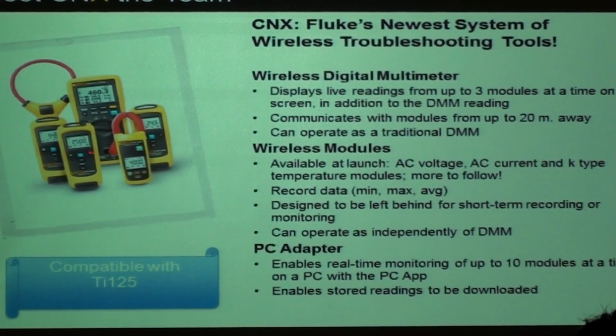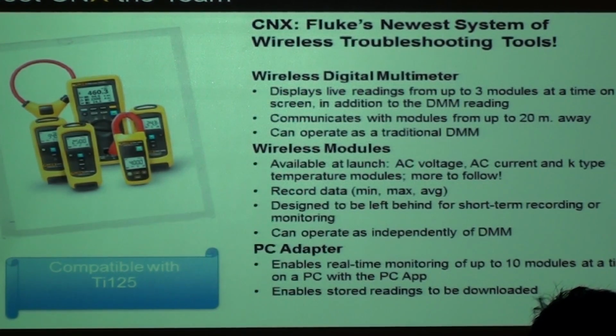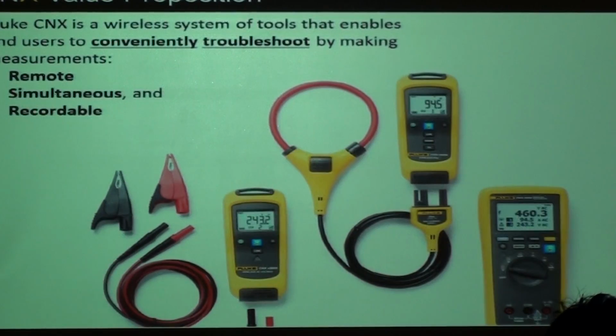You can log data, so you can leave these modules aside to keep recording. You can log the data, and then download all that data into the PC by means of a Bluetooth dongle. It's a nice little wireless device, and these devices are also compatible with thermal imaging. So with thermal imaging, I can look at a three-phase system. One of them is hot. What I do is clamp this onto the cable, and I can read the current reading on my thermal camera. So I have that extra power when I make a report, and know exactly what the current is to warrant my thermal imaging report.